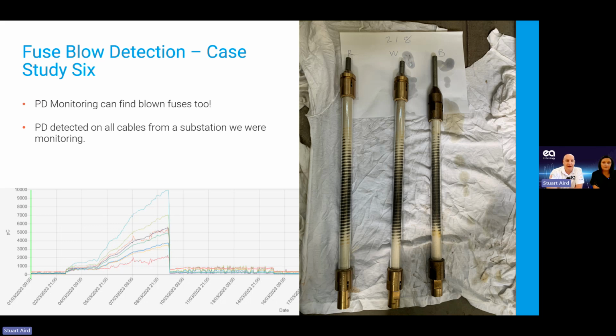And this is a case of that here, where we're actually monitoring a substation a few hundred meters away that was feeding this substation, and that was picked up on all the cables, because our cable monitor was on all the cables in the other substation, and it picked up the high levels of partial discharge activity. Again, we've seen it straight away. We can go and replace that fuse as quickly as possible, so it doesn't eventually track across the outside and lead to a failure. So I'd say the advantage of the monitoring is we know from day one that fuse has failed.